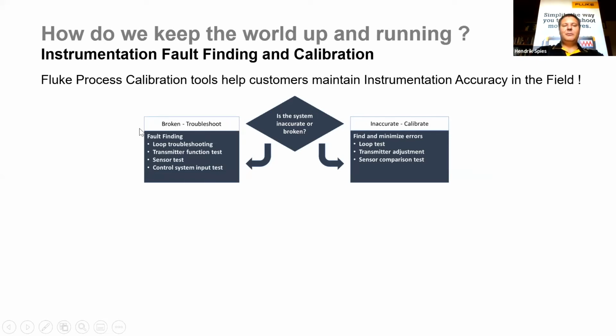If it's broken, obviously you need to do fault finding. And if you do fault finding on an instrumentation system, most of all, you're going to do loop troubleshooting. You're going to maybe look at a transmitter function. You're going to maybe do a sensor test or a control system input test, which is also sometimes 4 to 20 milliamp or voltage based. If you have inaccuracy, it means you need to calibrate. Then you need to find and minimize errors. So here you will do loop testing, some transmitter adjustment and sensor comparison. So this is a calibration, an as found, as left scenario.